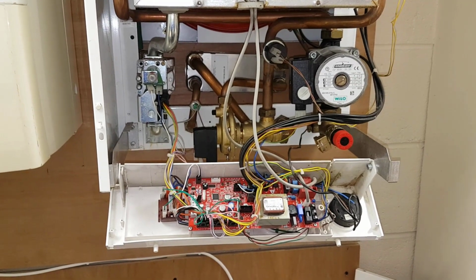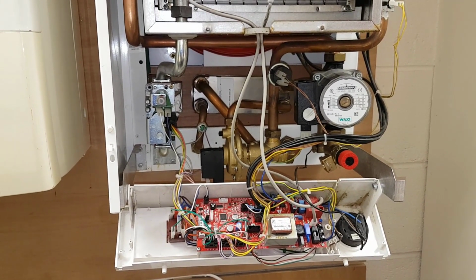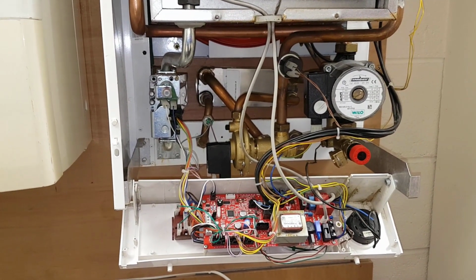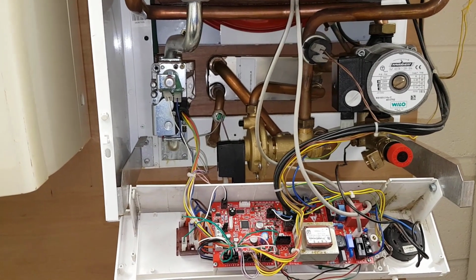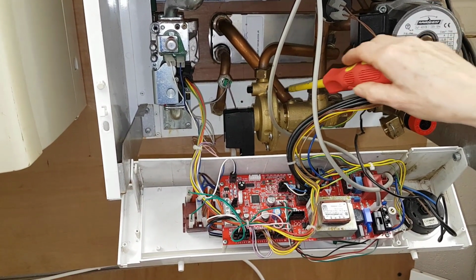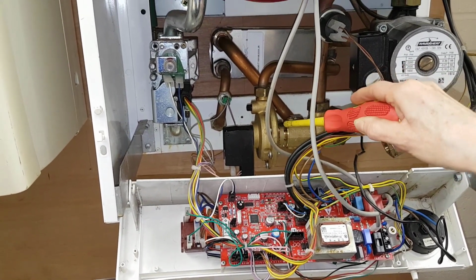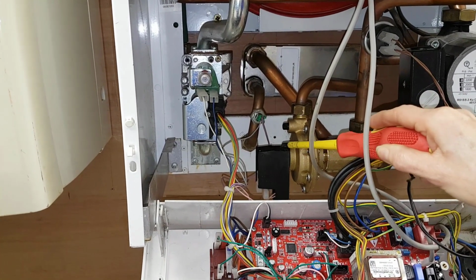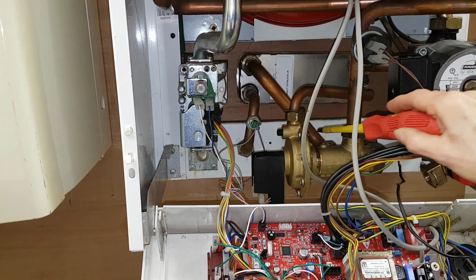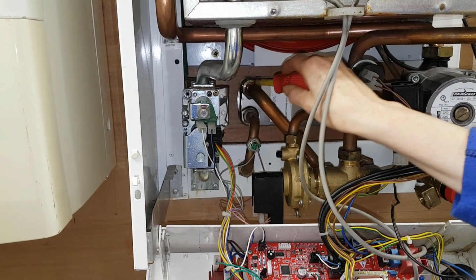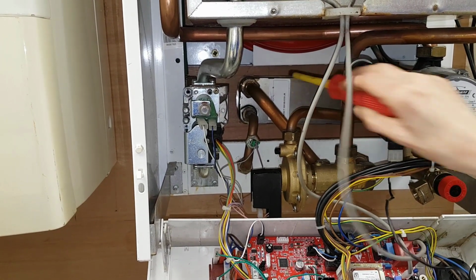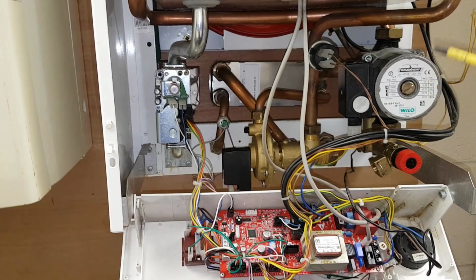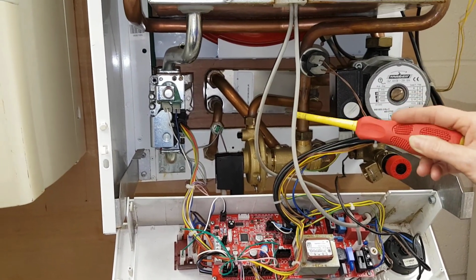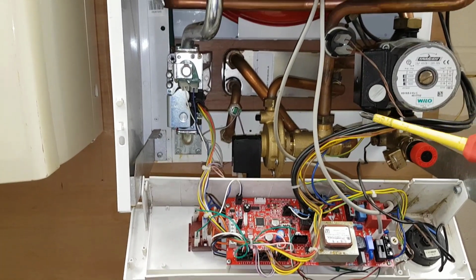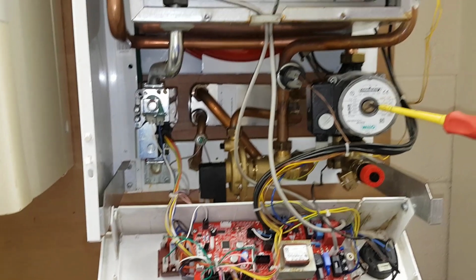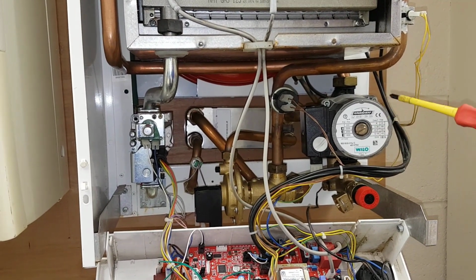So finally, what we're going to look at now is the hot water sequence. You're going to listen to Dan's description of that. The customer opens a hot water tap, which allows water to come into the diverter valve, which pushes out the diaphragm and makes a switch. That means the water will go to the plate heat exchanger, which is here, for the primary. So the primary water goes across here to here. But I'm talking about the ignition sequence now. The switch being out goes back to the PCB, which starts the pump. The pump then starts circulating.